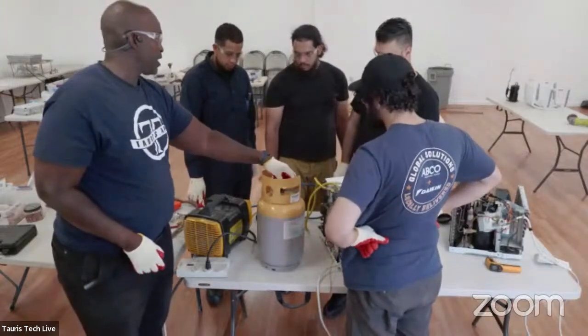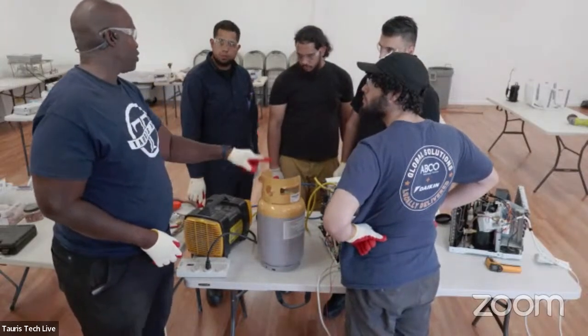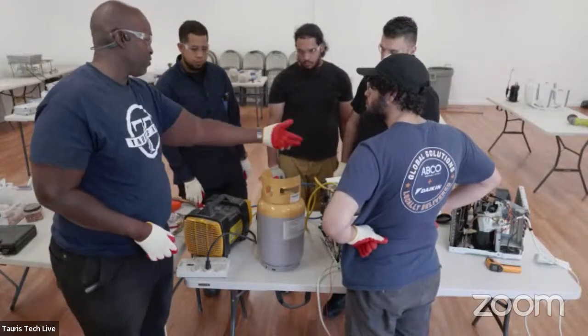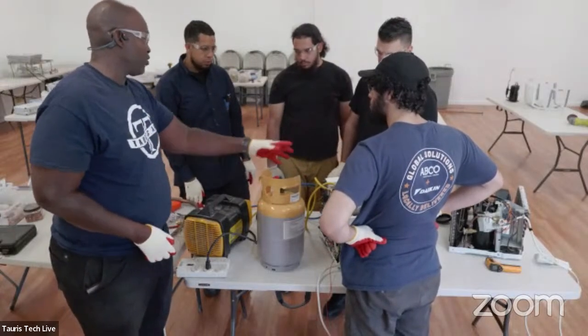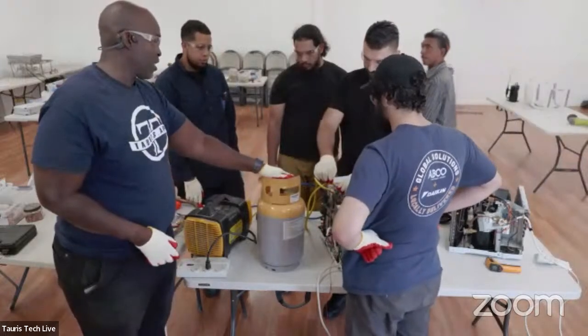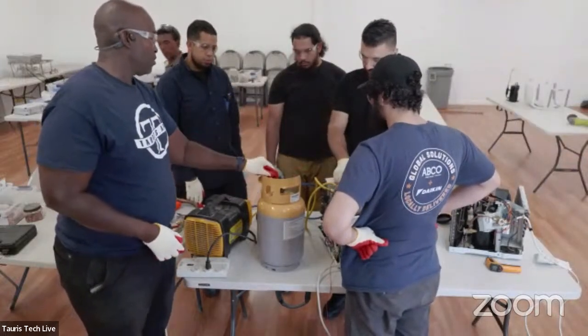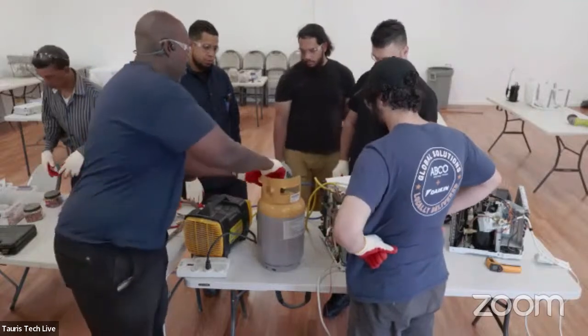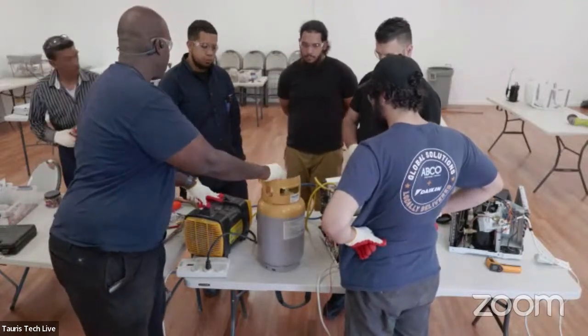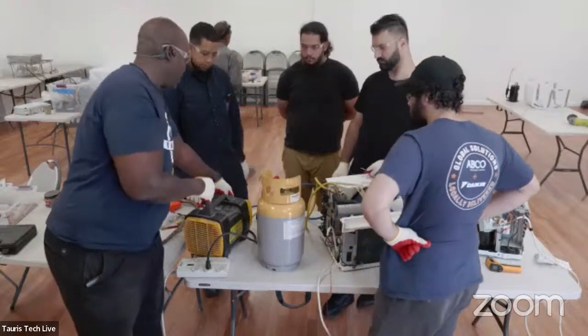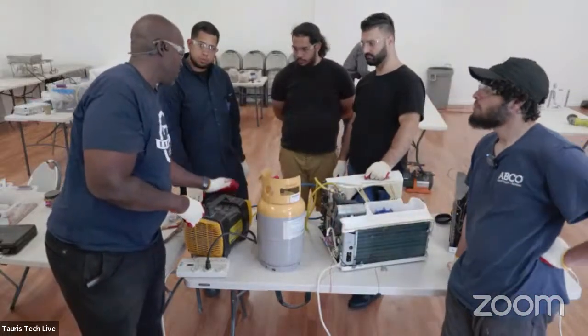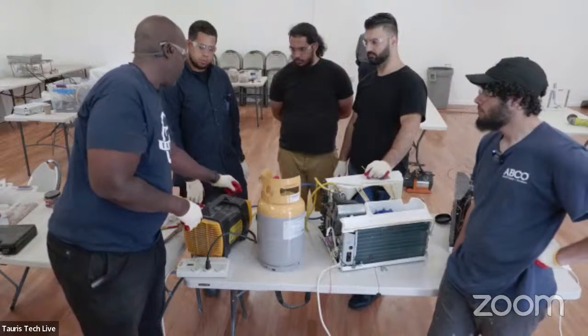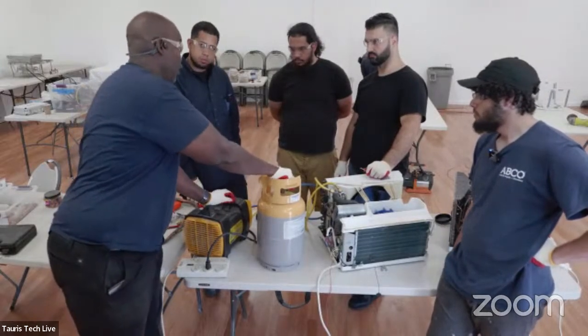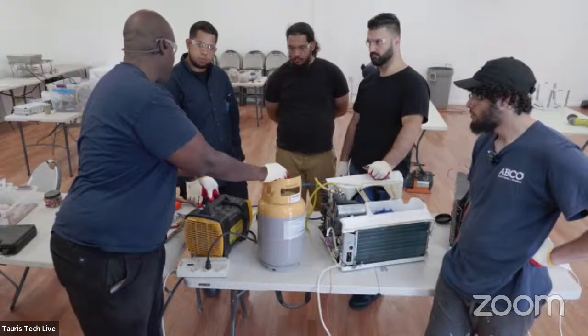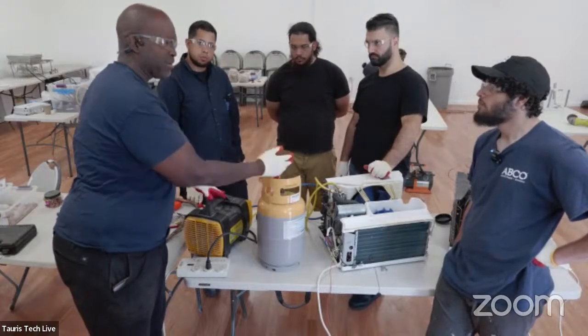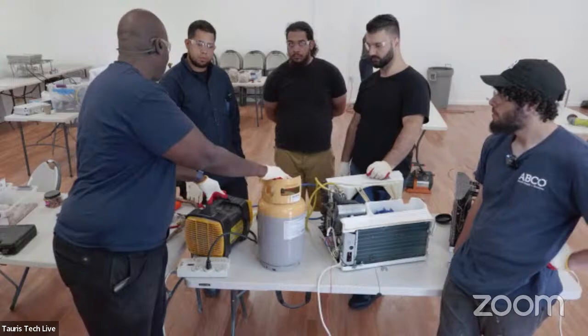So that's the difference between charging and recovery. Charging, I'm putting from the tank into the machine. Recovering, I'm taking out. In order to recover, since I can't turn the compressor on, I have to use this and make sure that this valve is closed. If I open this, refrigerant is going to spray out. If I run this machine with the discharge closed, the machine can't run like that, so it's going to turn itself off. If I run the machine with this tank closed, the pressure can build up. So sometimes you run it, machine turns off, it's like what's going on, and I open the tank.